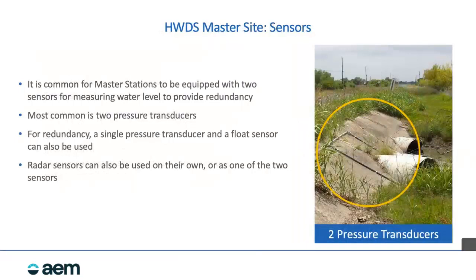No, we could use float sensors that trigger at a set level. We usually use dual floats for triggering the on and off position. Also a radar sensor, or you could use a bubbler. So virtually any type of water level sensor that's commonly used, we could interface with and use to trigger the action.